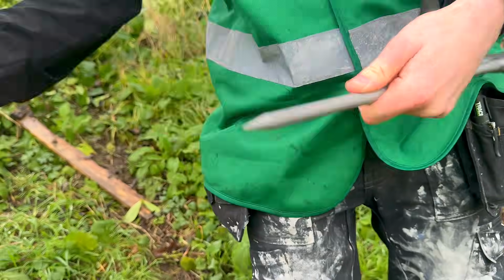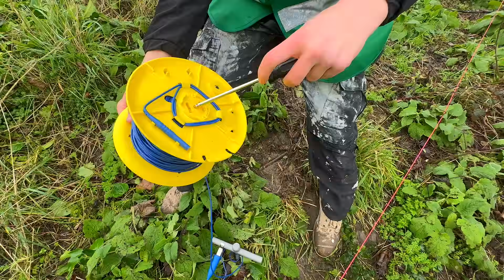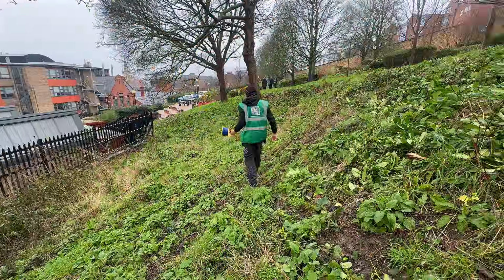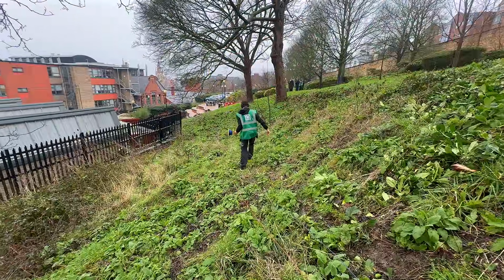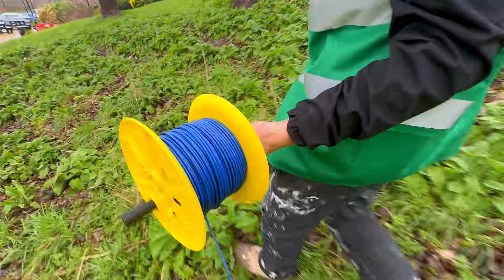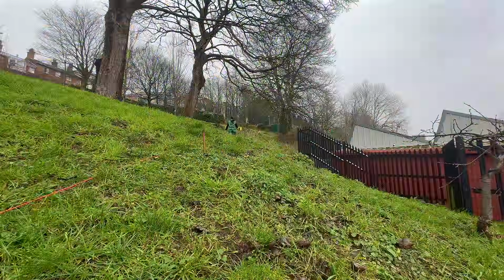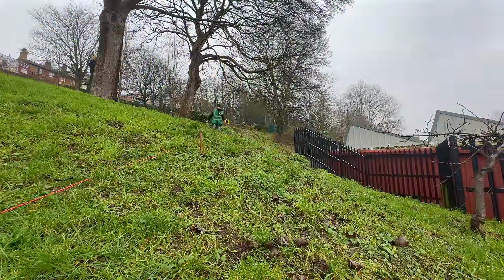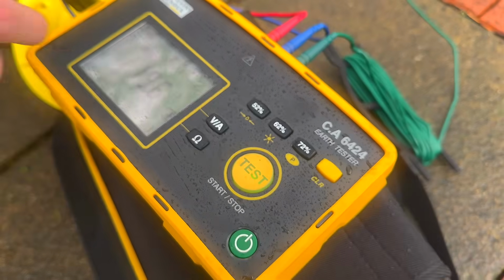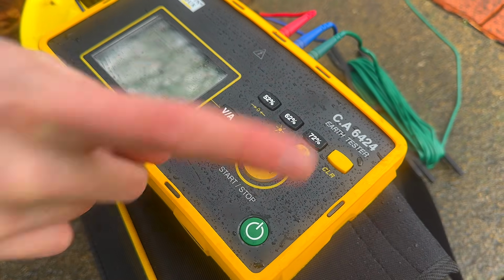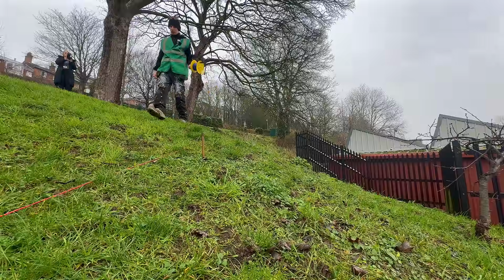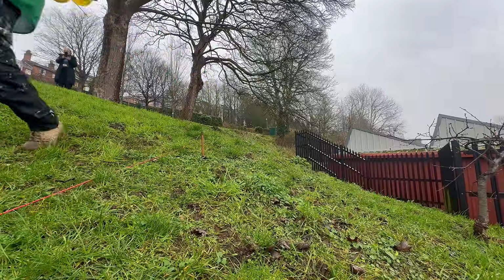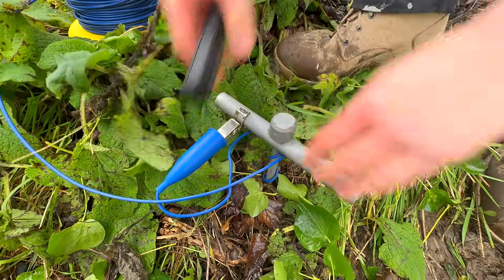Next we need to put the potential probe, in this case P2, between the electrode under test and the current probe C2. And it's really important that this is done in line with the current probe. But at what distance? Well, the common view is that it goes halfway between the electrode under test and the current probe, when actually the distance should be just over half the distance at 62%. We will find out why it's 62% in the next video. Okay, so 62% of 36 meters is 22 meters, so that's where we place our potential probe and measure. And we grab our readings and we make a note of it.